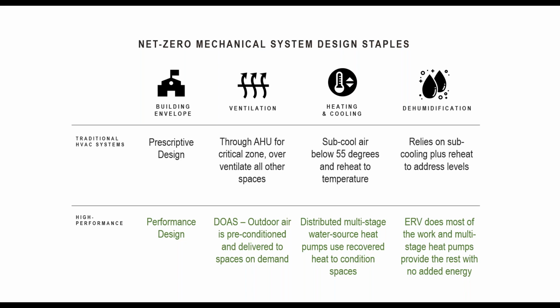In general, for heating and cooling, most of our zero energy projects have a distributed water source heat pump system. The thing about a heat pump system using a neutral water temperature loop is you get free heat recovery. It's inherent. As you reject heat into the loop in one space, another space that might need that heat, for instance at the perimeter of the building, is able to pull it back out of the loop and use it to heat the space very efficiently.